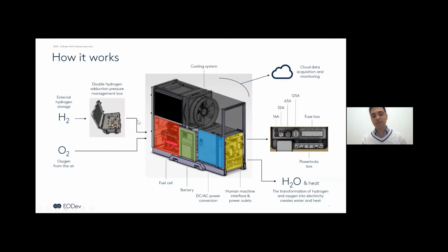We use the hydrogen inside the fuel cell compartment. As an electrochemical reaction between the oxygen and the hydrogen, we produce electricity. There's no combustion, no moving parts, which makes this equipment very silent compared to a diesel genset. As an output of this chemical reaction, we just have heat and water in the outlet. There are no carbon emissions, no NOx involved. We only have water, which can also be reused - it's hot water, not drinkable, but it can be reused for toilets, etc., and heat in the outlet.